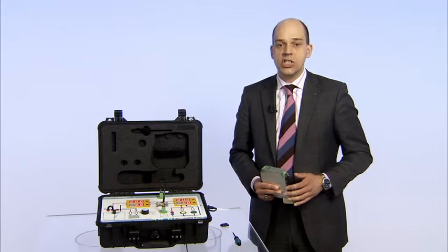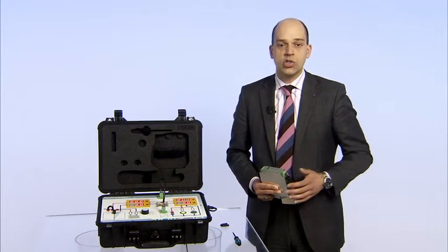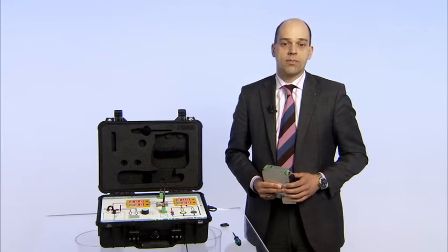The fourth benefit, heavy loads are reliably started by the static power boost power reserve with 1.25 times the nominal current. The final benefit is that the preventative monitoring function reports critical operating states before faults occur. This is implemented through continually monitoring the output voltage, output current, and input voltage.